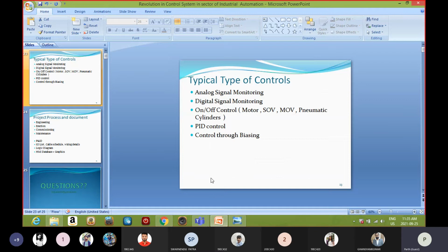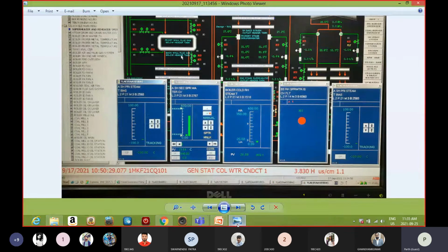that normally people use. So for each control, we have a dedicated faceplate. If I click on any of the objects, this faceplate will appear. The faceplate will appear according to the type of the object. Now, for example, this is 27.2 coming. If I click on this, the faceplate will open like this, because it is an analog input.